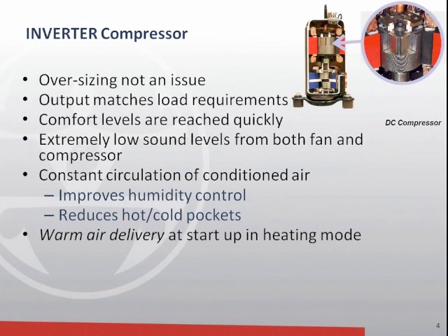Conversely, when you're in the heating mode, it throttles up and down, but when you first start, it actually holds the indoor fan off for a period of time until that coil is nice and hot, and then the first breath of air that the occupant feels when that system comes on is above 100 degrees, feels nice and warm and toasty to them, again solving a typical complaint that people have about heat pumps that are putting out cold air or colder than body temperature air in the heating mode. These systems are designed in all cases to put out temperatures above 100 degrees. It's above body temperature. It feels warm. It feels good as the space is being conditioned.